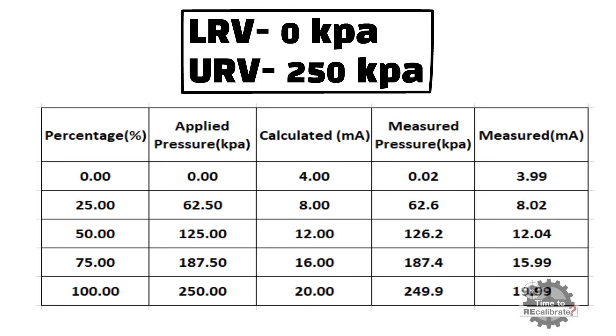When there is 25% input, the standard analog output value is 8 milliampere. And when there is 50% input, the standard analog output value is 12 milliampere. The standard analog output value is 16 milliampere for 75% of input. And the standard analog output value is 20 milliampere for 100% of input.